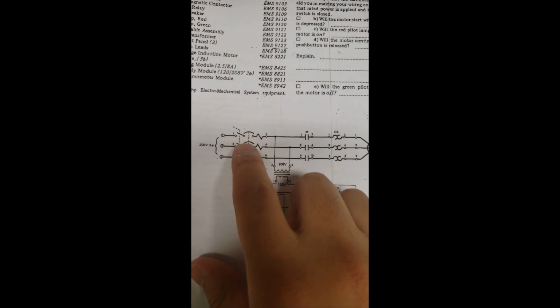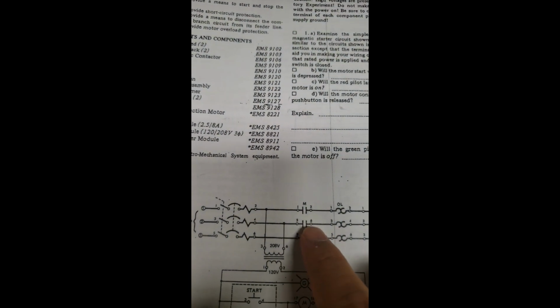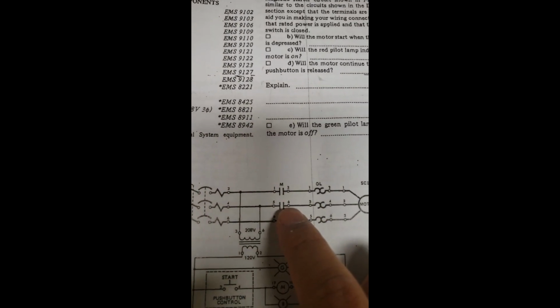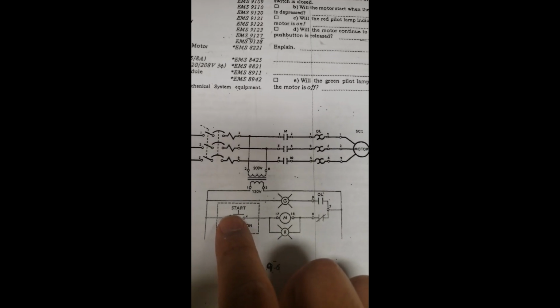Now, if I close the circuit breaker here, this one, if I make it on, nothing will happen. Why? Because this is a normally open contact, so the current will not pass through this contact. It will stop here. In order to make this contact normally closed, I have to energize this coil. So by energizing this coil, I have to press the start push button. If I press the start push button here, the current will go through the coil. The coil will be energized. This one will go down, and this normally open contact will be normally closed. Then the motor will start.